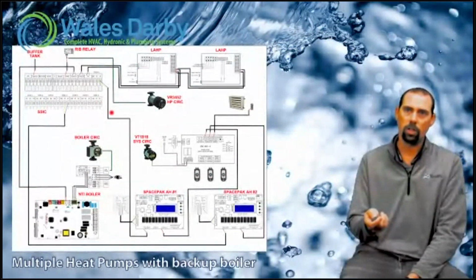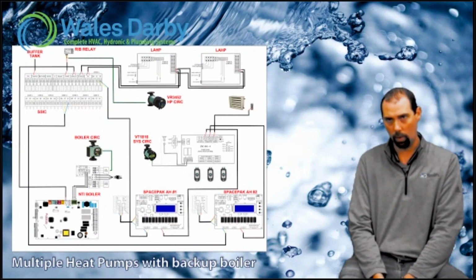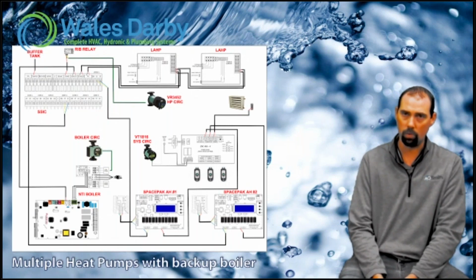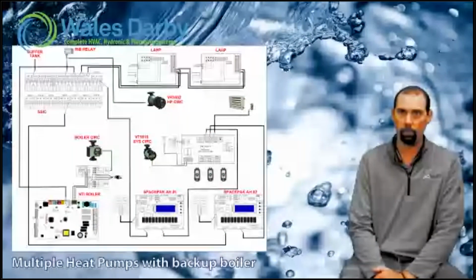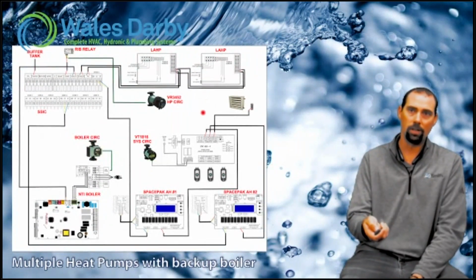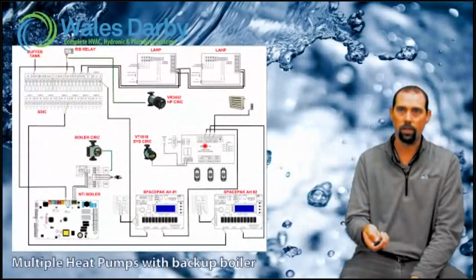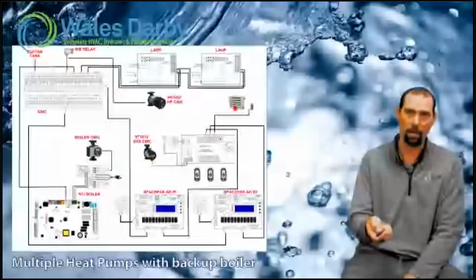Circulators, again, this initial diagram we ended up moving to wiring these things with 2 separate pumps, each one has its own dedicated circulator. So those changed a little bit, but utilizing something else you guys already know, Taco zone control. So we got our 3 zones coming in, and we got our hydronic air handlers as well as our Modine going to some zone valves.